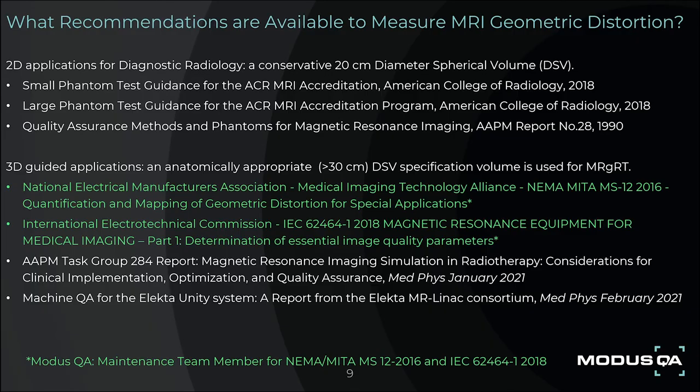Several standards bodies and professional medical and scientific societies have recommendations on methods of measuring image quality parameters, with specific guidelines related to measuring 2D and 3D geometric distortion. Historically, recommendations have been biased towards 2D applications for diagnostic radiology, with testing specifications defined over a conservative 20 cm DSV. National and international standards have been updated to address the growing use of MRI for advanced 3D-guided applications with larger 34 cm DSV specification volumes, appropriate for MR-SIM and MR-Linac QA, with further recommendations released this year by the AAPM Task Group 284 and Elekta MR-Linac Consortium for MR-SIM QA and MR-Linac QA, respectively.